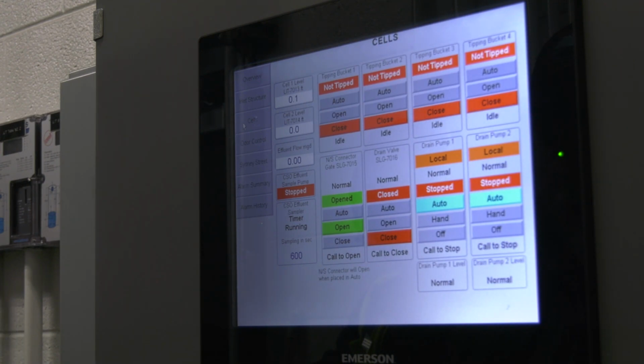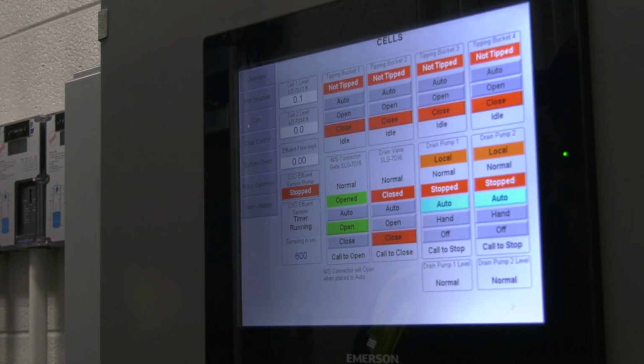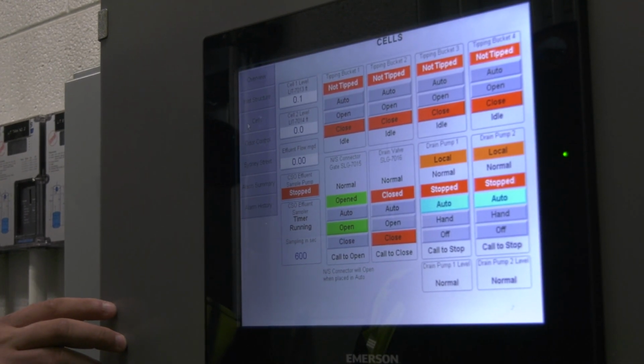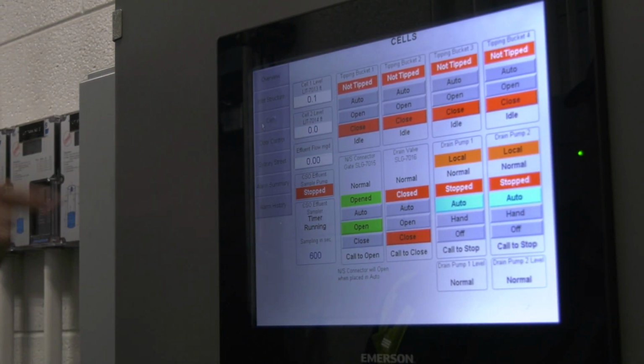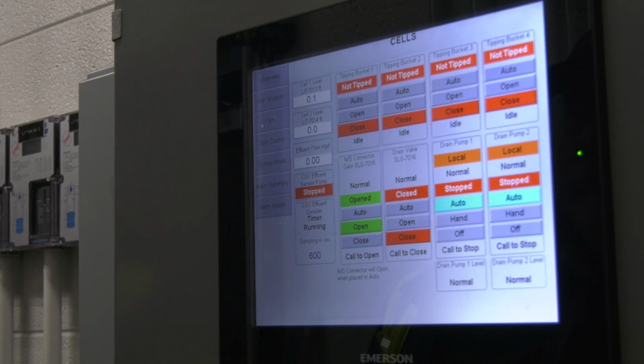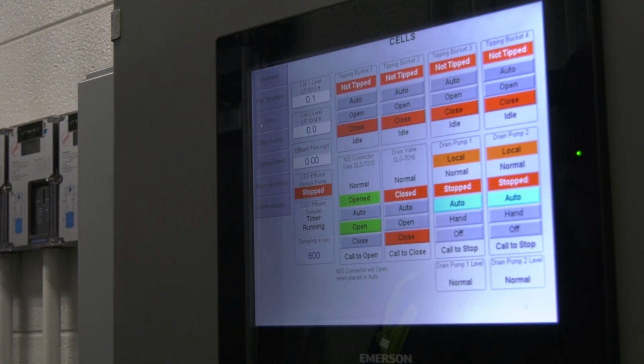All right, tipping buckets. Tipping buckets are controlled in sequence. The sequence below will be started when the cell's low flow input turns off. So bucket 1 is called to tip. Are you guys running these tipping buckets in automatic? No. Okay. We just turn them to open, which opens the solenoids, and then we go down there and turn each bucket on manually. You guys aren't doing any automatic control of tipping buckets, are you? No. Okay.